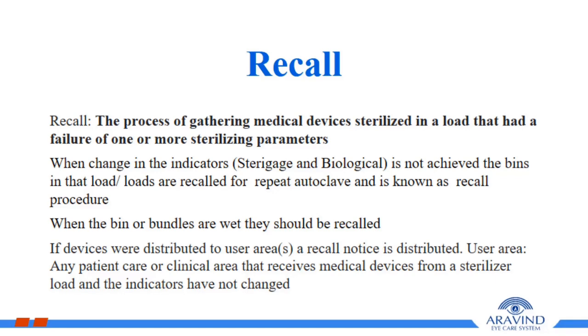The process of gathering medical devices sterilized in a load that had a failure of one or more sterilizing parameters is known as recall. When change in the indicators is not achieved, the bins in the load are recalled for a repeat autoclave, and this is known as a recall procedure. Or when the bin bundles are wet, they should be recalled. If devices were distributed to the user area, a recall notice is distributed.